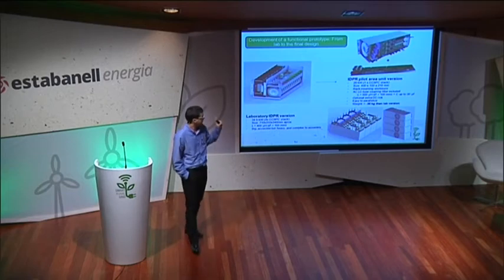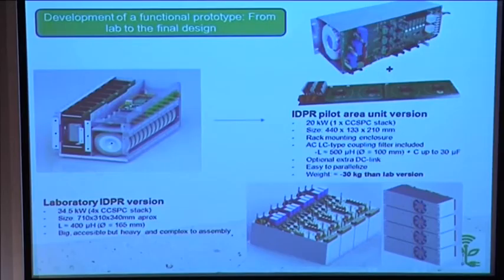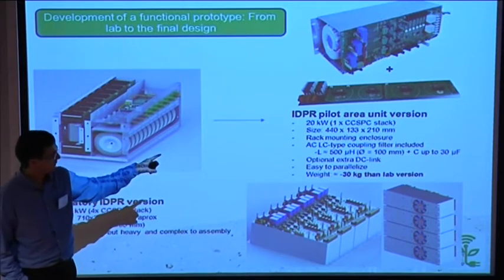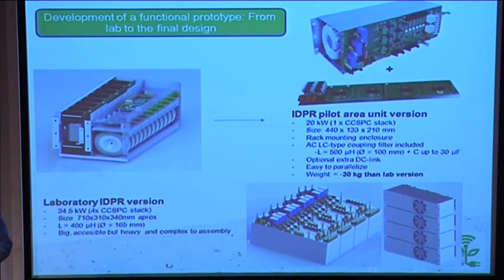We are talking now about 20 kilowatts. This is just one cell, so it only integrates one silicon carbide module, but the size is reduced. We have used a rack-mounted enclosure to facilitate assembly in case we want to parallelize the system. We have also included not only the inductive filter, but also the capacitive filter.